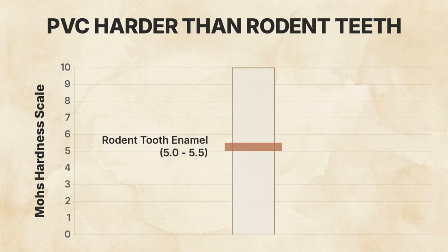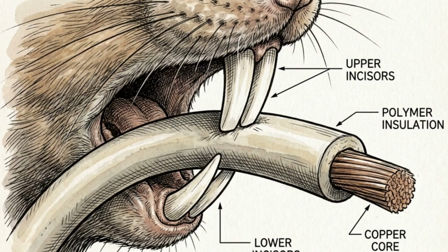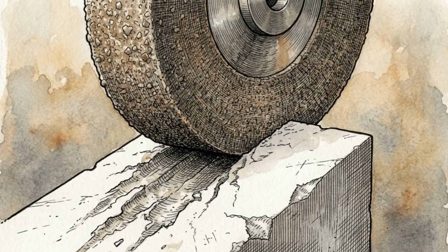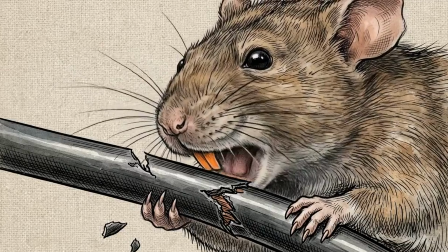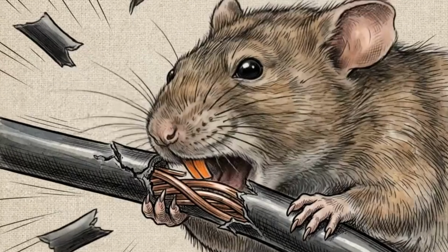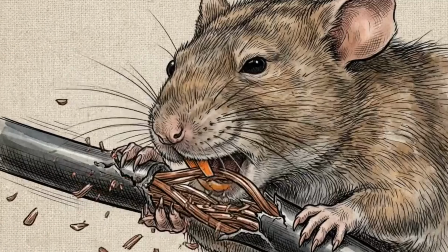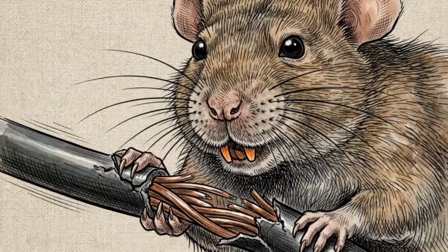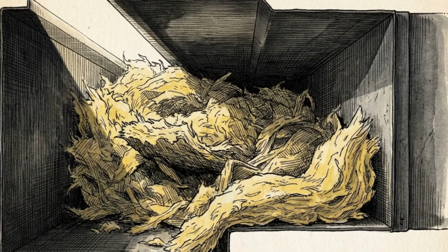On the Mohs scale, rodent tooth enamel sits around 5.0 to 5.5. The titanium dioxide in the PVC coating hits a 6.5. Rather than eating the system for food, the rodents are using our advanced synthetic polymers as an industrial grinding stone. They strip the coating away just to wear down their teeth, leaving the system's critical electronics entirely exposed to short circuits. Once inside the ductwork, the rodents cause a secondary layer of structural damage.